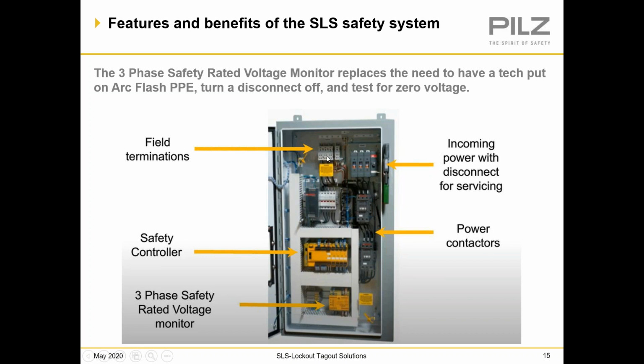For instance, you have the field terminations, which is self-explanatory. We have a safety controller, which is in this particular photograph, a multi-configurable safety relay. And you have the three-phase safety rated voltage monitor down here. Remember earlier we talked about this replacing the manual means of testing for zero voltage at the source. So that three-phase rated safety monitor replaces the need to have a tech put on arc flash PPE, turning a disconnect off, and testing for zero voltage. It's all done automatically within this three-phase rated safety rated voltage monitor.